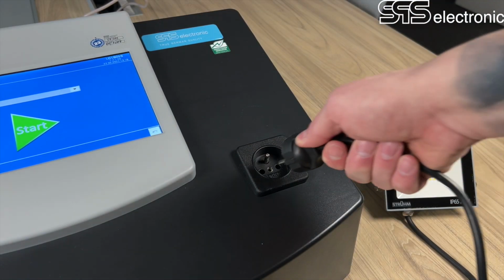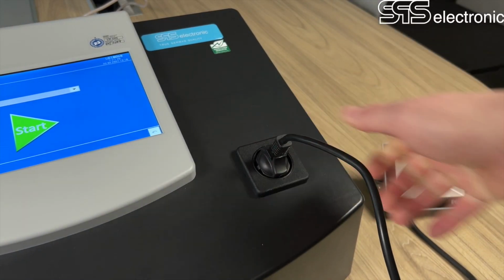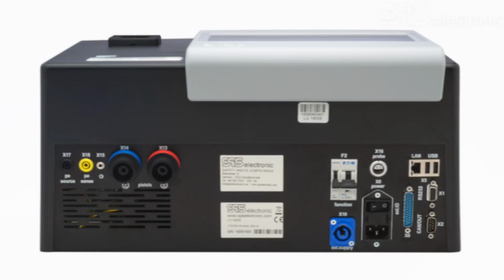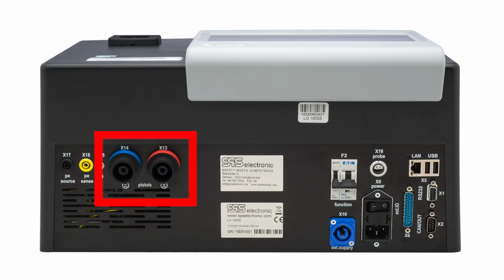Connect your DUT into the socket. Our DUT will be this light. If your DUT doesn't have a plug cable, you can use high voltage connectors from behind. No safety equipment is required because this model is safety current limited.